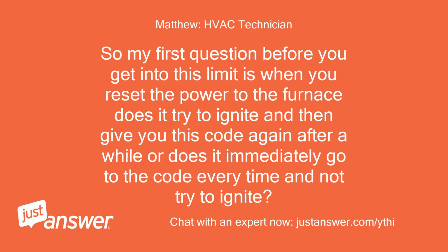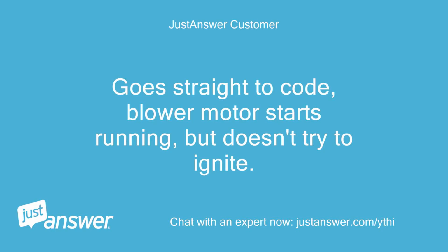So my first question before you get into this limit is, when you reset the power to the furnace, does it try to ignite and then give you this code again after a while, or does it immediately go to the code every time and not try to ignite? Go straight to code, blower motor starts running, but doesn't try to ignite.